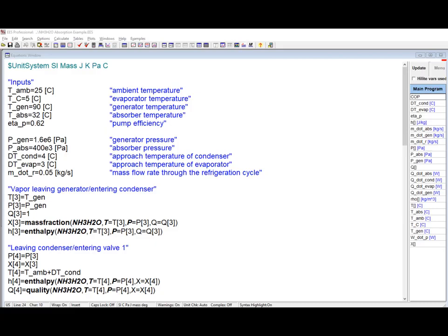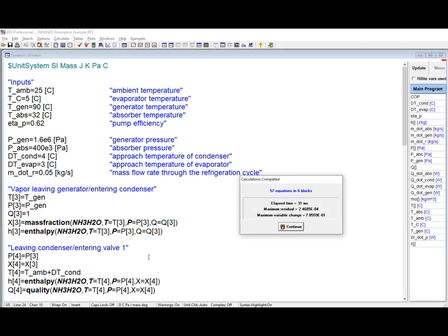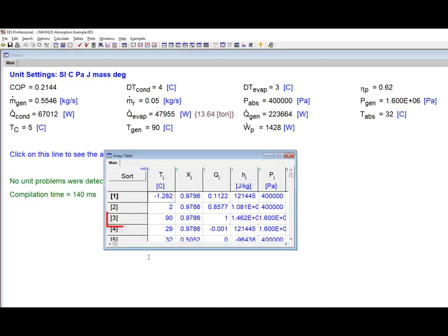The EES file that simulates this cycle begins by setting the unit system using the dollar unit system directive and then by entering the known information. The flow leaving the generator here at state 3 is at the generator pressure and temperature and its saturated vapor. Therefore, its state is fixed by P, T, and Q or quality. Here we get the mass fraction and the enthalpy at this state and you will notice that the mass fraction is 0.9786. So this flow is almost 98% ammonia with very little water in it.